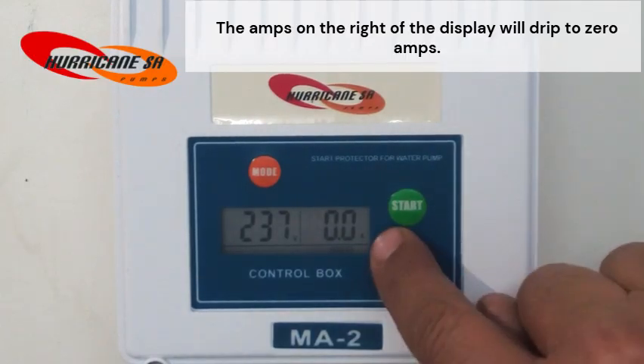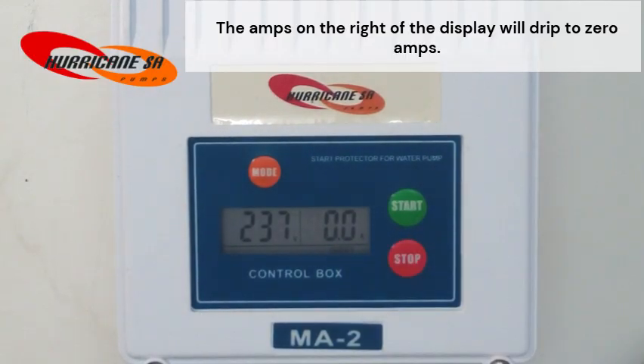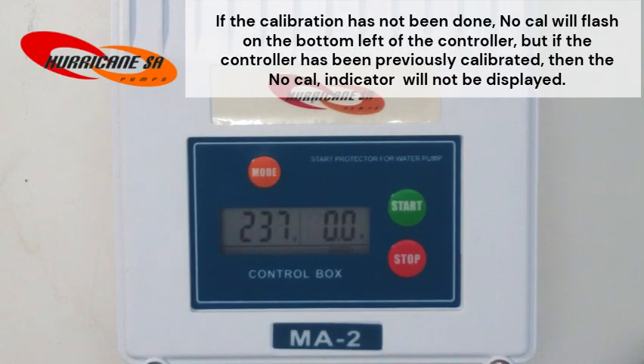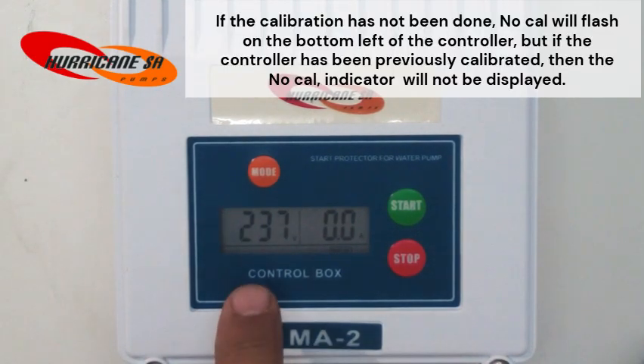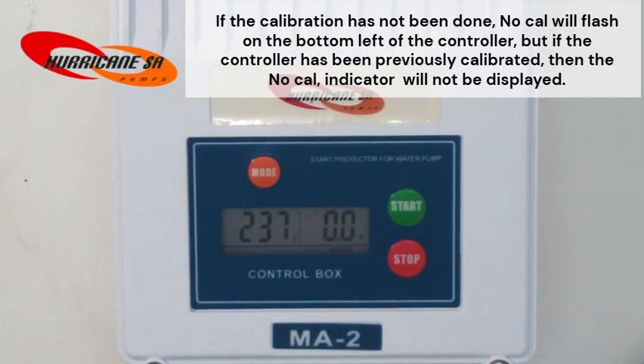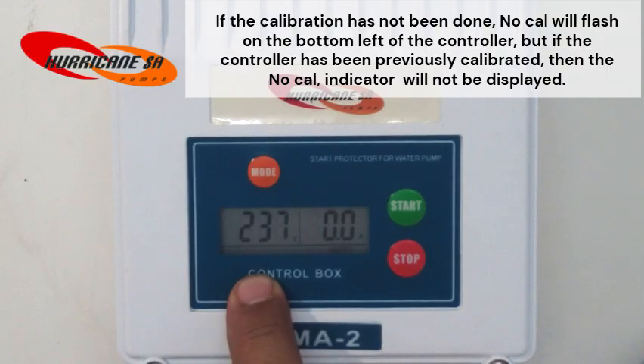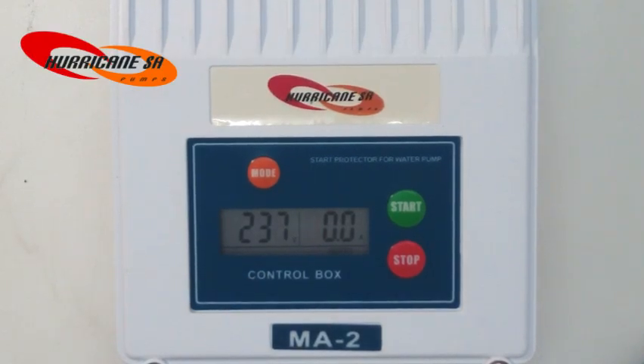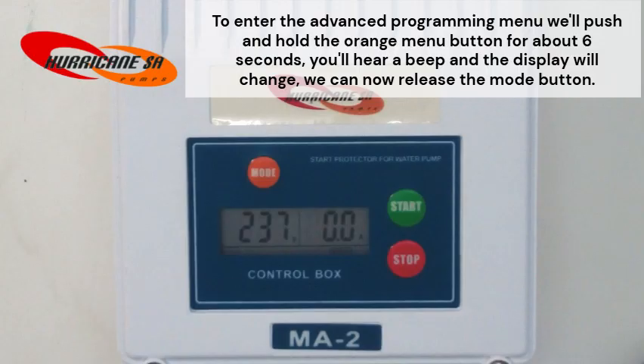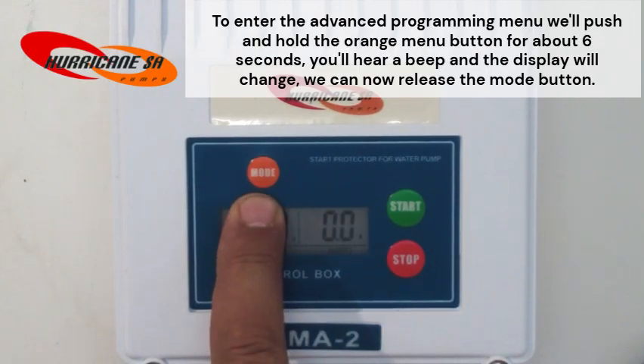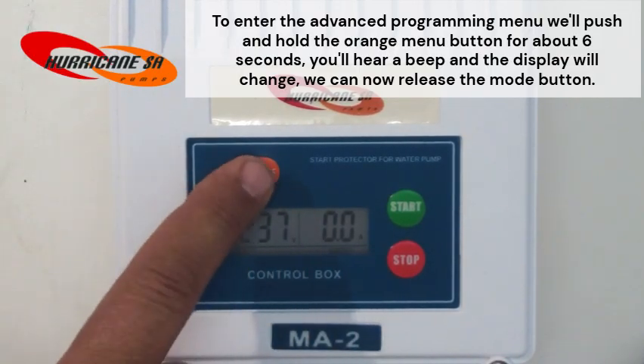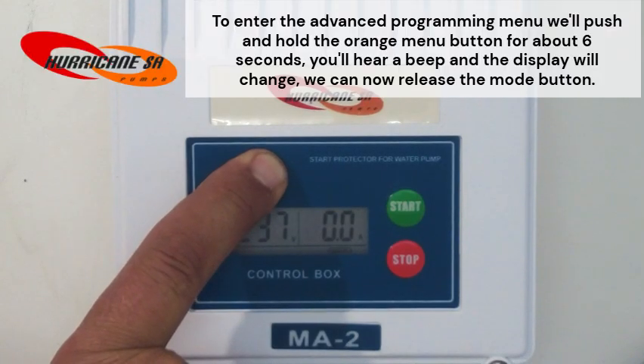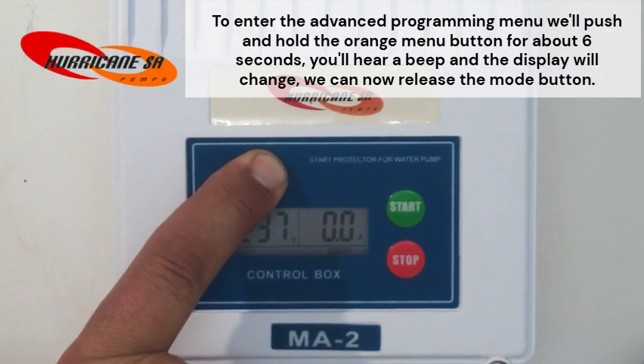The amps on the right of the display will drop to 0 amps. If the calibration has not been done, no cal will flash on the bottom left of the controller. But if the controller has been previously calibrated, then the no cal indicator will not be displayed. To enter the advanced programming menu, we'll push and hold the orange menu button for about 6 seconds. You'll hear a beep and the display will change. We can now release the mode button.